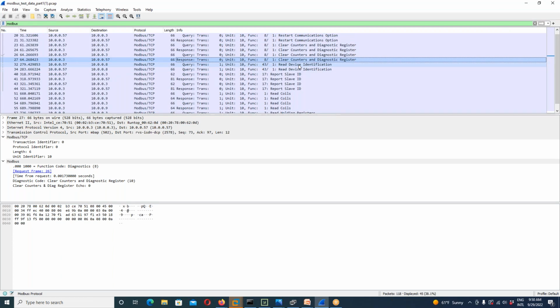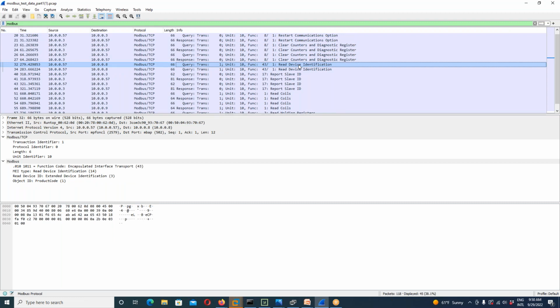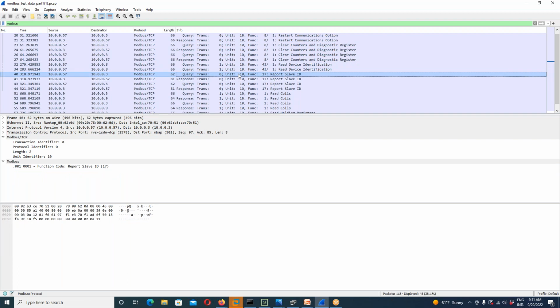Then read device identification, function code 43, encapsulated interface transport, read device ID, object ID, product code 1. You see these two packets communicating here. Then we have report slave ID, function code 17.